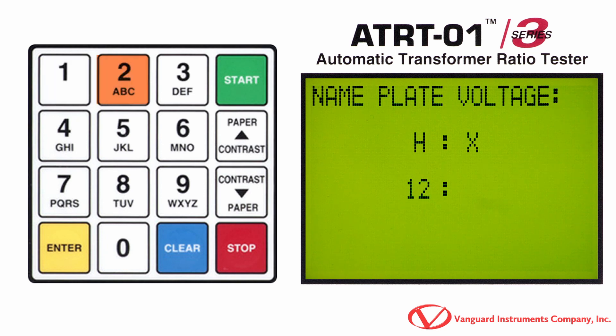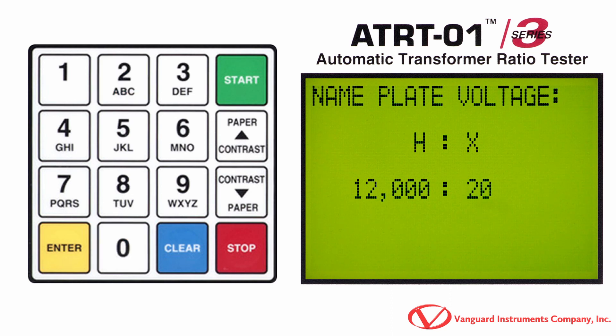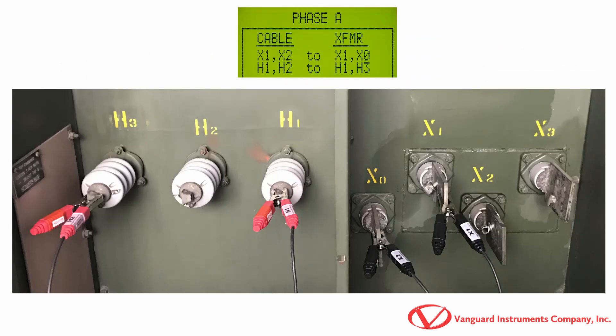Enter the H nameplate voltage value and press the Enter key. Enter the X nameplate voltage value and press the Enter key. Now we are given instructions on how to connect our cables to test phase A of the transformer. Please note that this will be different for each transformer type and also whether the X0 terminal is accessible or not.